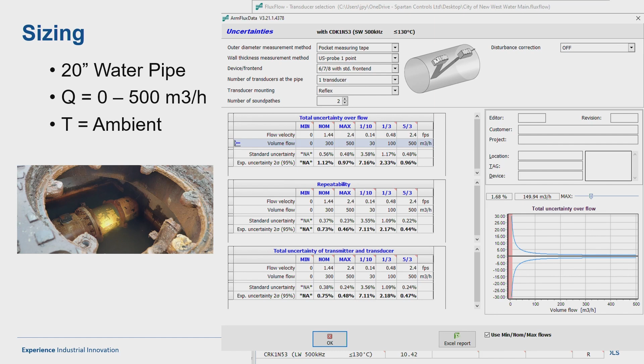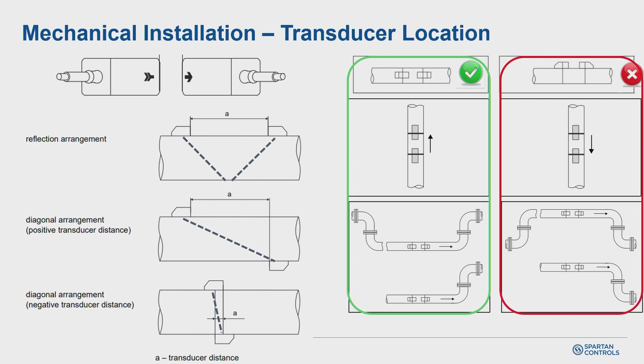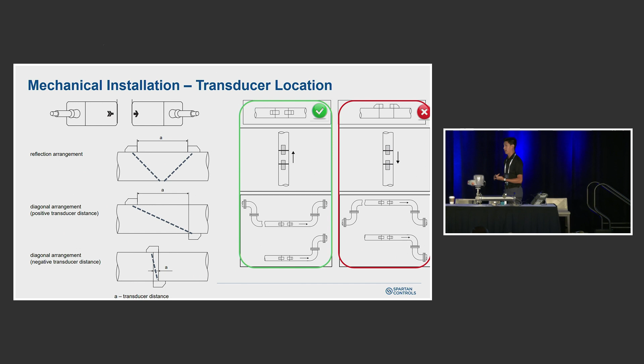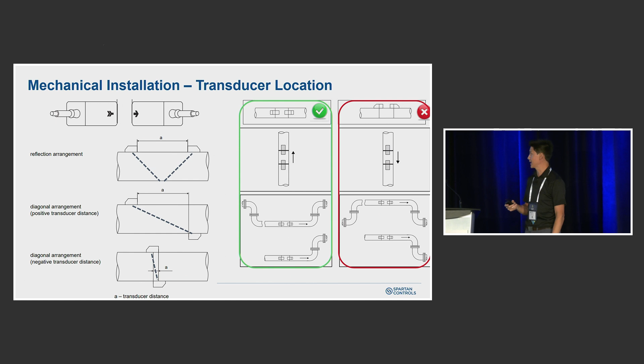Okay, installation best practices. So this is kind of key. On all of our transducers, we have an arrow that points together. And when we talk about the separation distance, we're talking about the face-to-face between those transducers. And typically, we want the transducers to be mounted in a way that they never get interfered with. So if there's any potential for sedimentation on the bottom of your pipe, then we typically don't want those transducers mounted at the bottom. So we want them to be on the side. And of course, we want the pipe to be full as much as possible. So this is why ideally we have a vertical up orientation. And we typically don't want the product to be falling through the transducers. And we don't want them to be at high points, because that's where you can start to have pipe that isn't full.